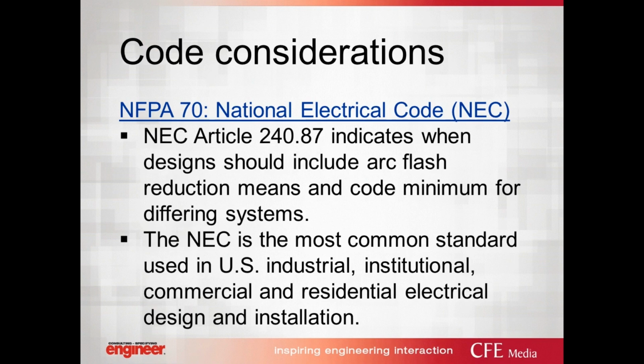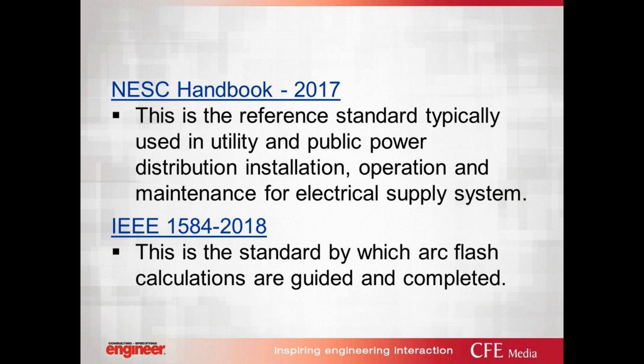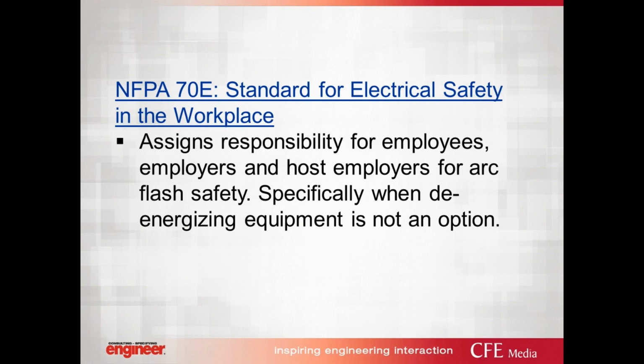for industrial, institutional, commercial, and residential electrical design and installation. 110.16 gives us the marking requirements, while 110.21(B) gives us the information that is required to be on these markings. The NESC handbook, which is published by the IEEE, is typically used in utility and public power distribution and installation for operation and maintenance of our electrical supply system. IEEE 1584, 2018 edition, is required for arc flash calculations and tells us how these calculations are guided and completed.